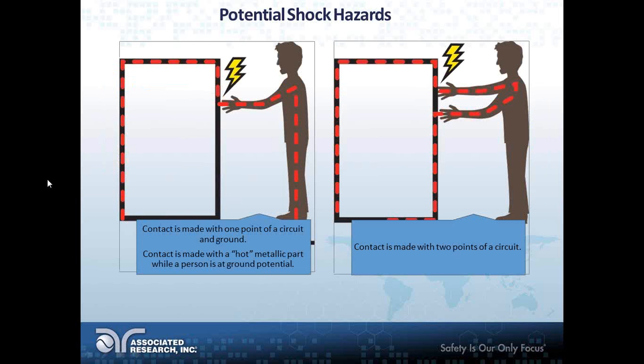Let's look at some potential shock hazards. They come in several variations, but these are the main ones we tend to run into. On the left-hand side, Abraham Lincoln is touching something energized—he's made contact with one point of a circuit while he's at ground potential. So he's touching a hot point, and current is flowing through his arm, down his body, and into the ground, because the current has found an attractive path through him. One thing to realize is that electricity is lazy—current takes the path of least resistance, and if that path is you, it's going to take it. It doesn't consider whether you might get hurt.